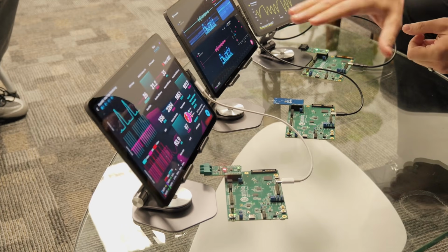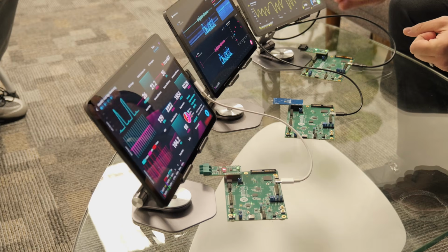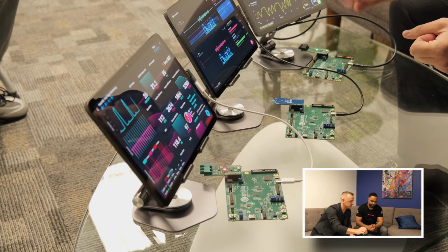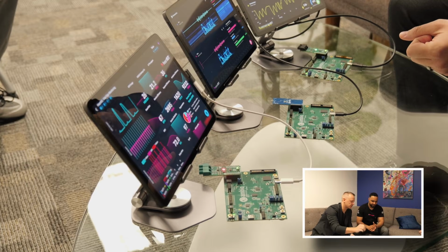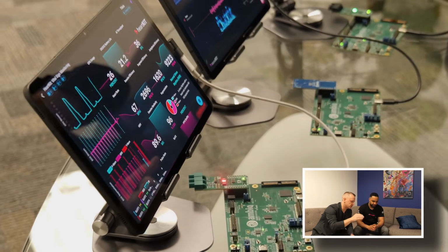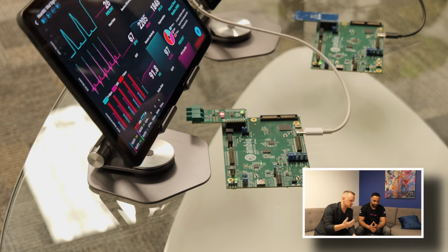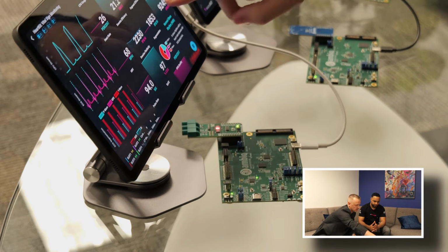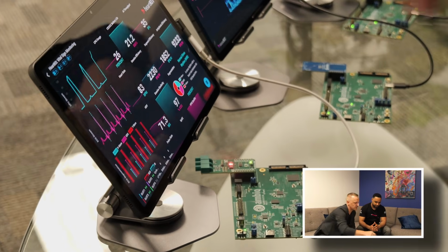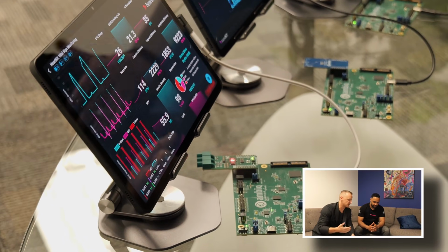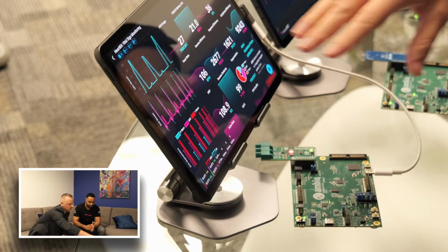It's a bit busy, what's going on here, but what we're showing is we're streaming ECG as well as PPG signals. And right now we're running 3 different AI models. You imagine an ECG signal as you're wearing it is going to be highly noisy. So the first thing that we do is denoise the signal. And that's what we're showing here with the model and the efficiency that it's gaining. The next thing you want to do is segmentation, right? If you're looking for heart attacks, you're looking for AFib, you're going to want to know where the P, the QRS, and T wave is. So we actually do segmentation, which you can see here. It's identifying all the different parts.